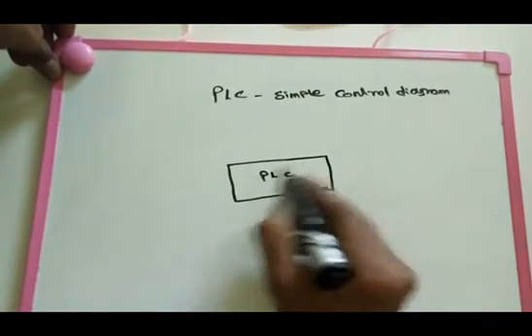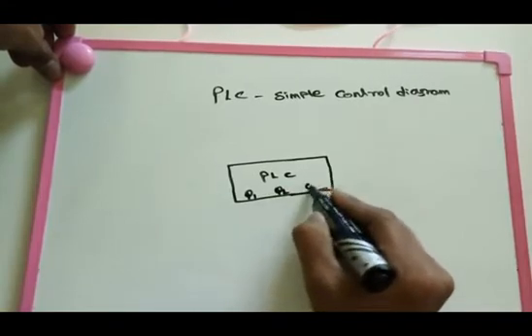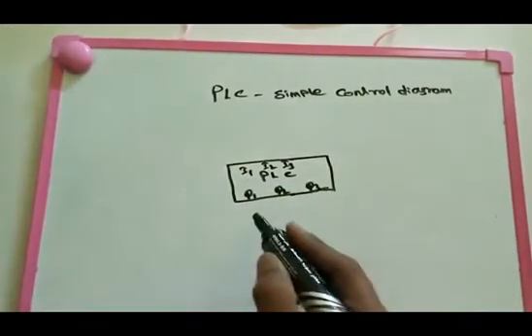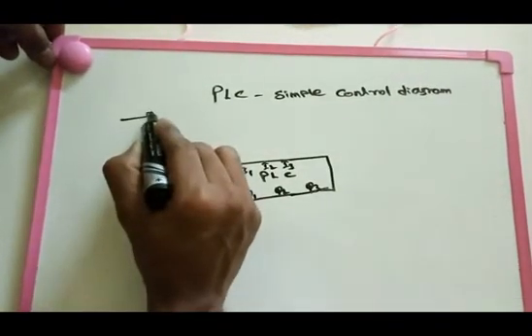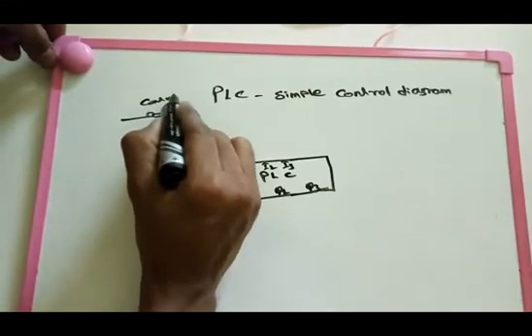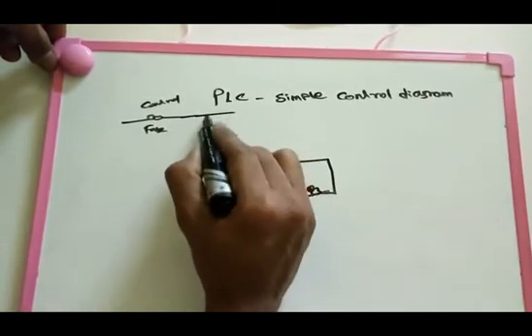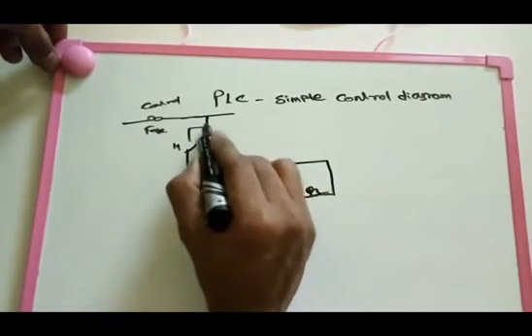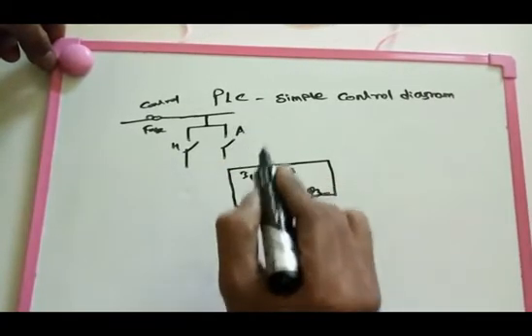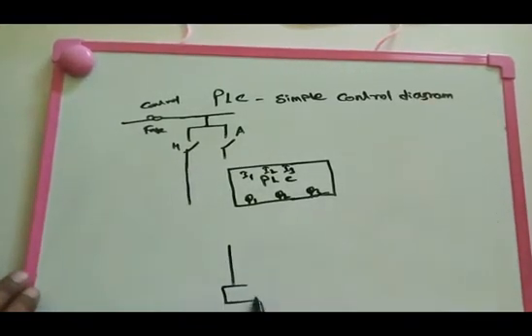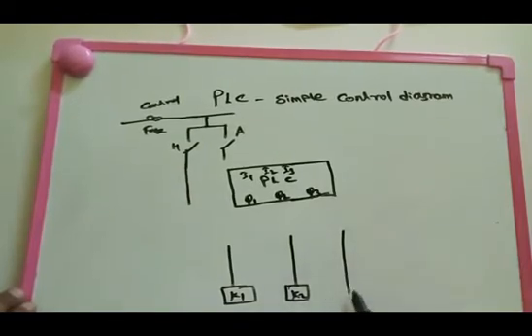The PLC outputs are Q1, Q2, and Q3, and the inputs are I1, I2, and I3. The actual supply is given separately. This is the common power supply with a control fuse. After that we make the Hand and Auto modes. The Auto function gives a feedback signal — one of the feedbacks goes to the inputs. The Auto function will directly operate contactors K1, K2, and K3.